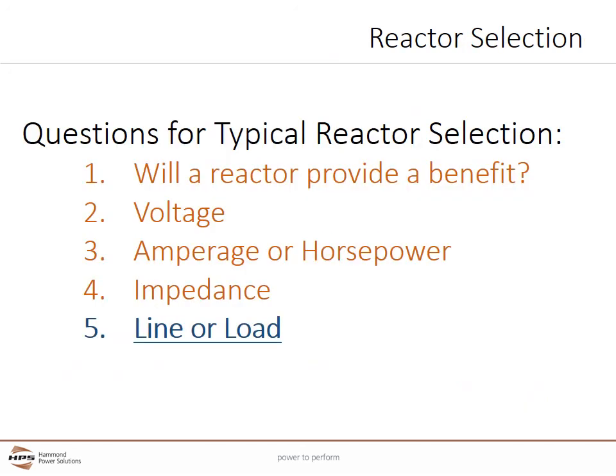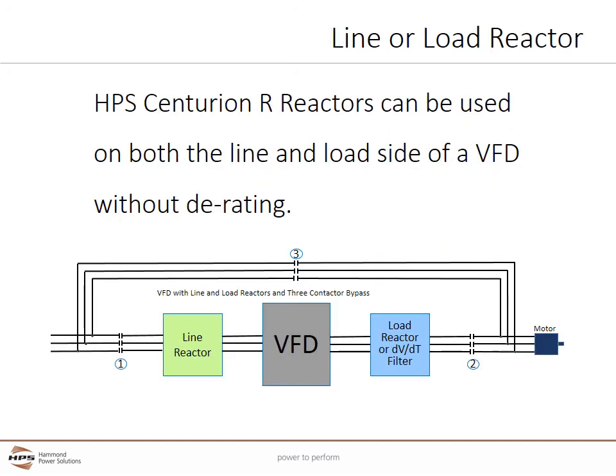Lastly, let's look at determining if we need a line or load reactor. Some manufacturers have separate reactors for line side or load side that cannot be interchanged, as the load side is a little rougher on reactors. HPS makes this easy: the HPS Centurion reactors can be used on both the line or load side of the VFD without any derating, as long as the current ratings are met.